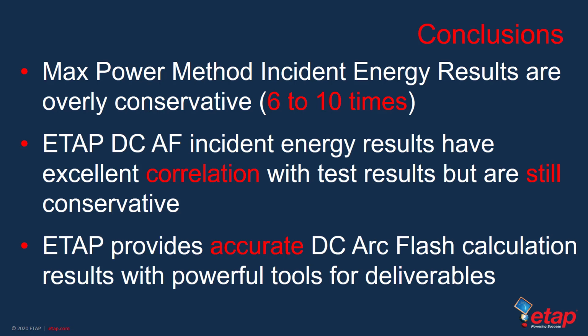And of course, in order to really get a formal answer or a formal unifying way of doing DC arc flash analysis, it is my humble opinion that we need to start a similar standard like IEEE 1584-2018 that will unite or coalesce all the DC arc flash calculation methods. Hopefully, we can continue the education process and eventually reach consensus on a single method. For now, we have seen that when properly configured, ETAP results have excellent correlation with test results. However, I would encourage the study engineer to contact ETAP to establish a discussion on what parameters to use for each type of system.